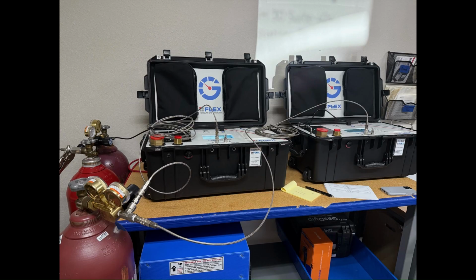The other way that you can troubleshoot an analyzer is to compare it with another analyzer. Here we have a T-piece hooked up to a regulator and a brand new bottle, and we're going to run tests simultaneously off the same gas sample to compare the different results from the analyzers. This is a great way to compare also our analyzer with other analyzers to see which one you like the best. Hopefully it's the Flex.